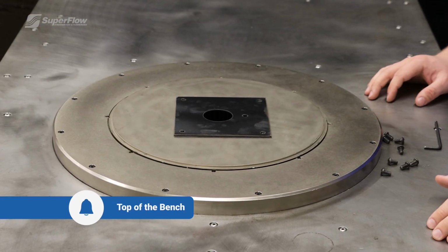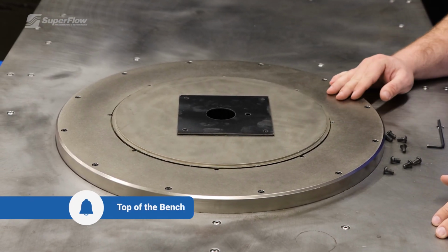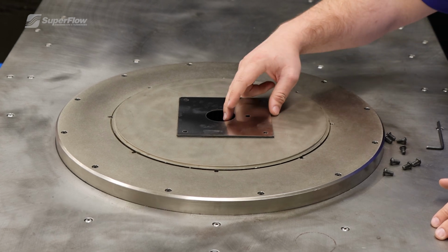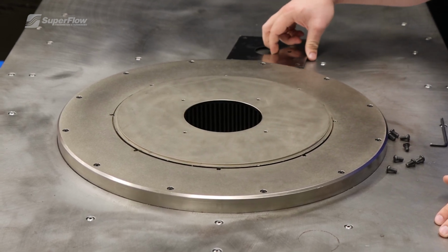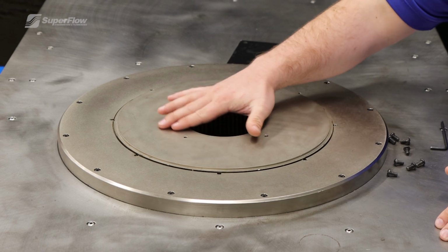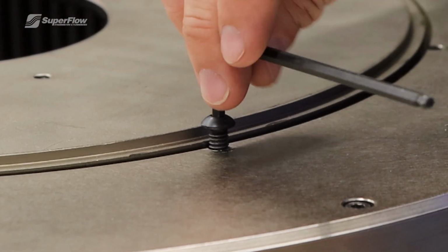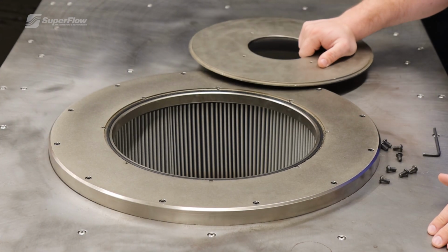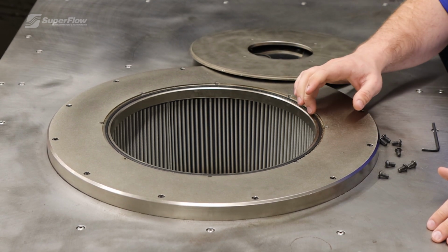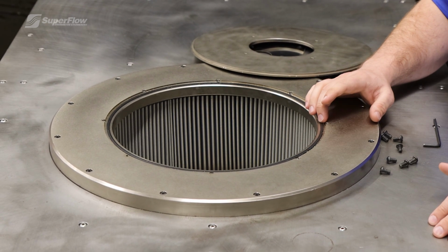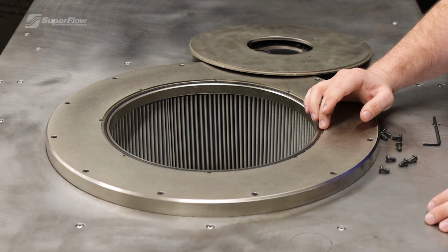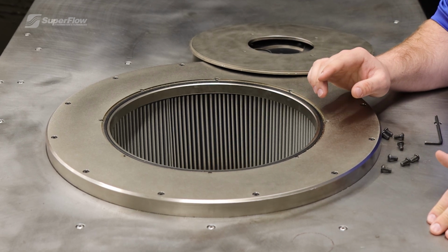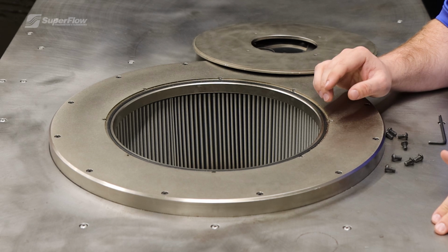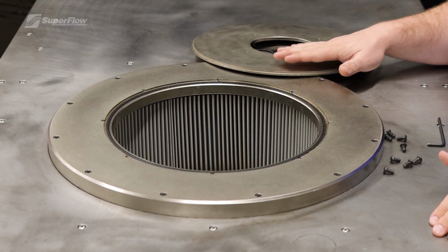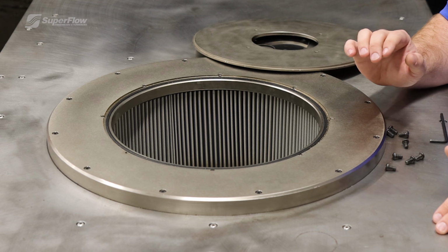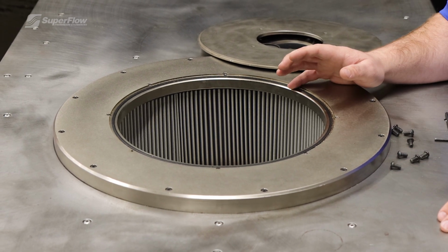Moving to the top of the bench, you see this is our Orifice plate assembly. On top right here, we have our daily reference plate. Beneath that is the main Orifice cover. It is housed under 8 screws. I removed those already. And beneath that, you'll find your sealing gasket. It's important to inspect this frequently for any cuts, cracks, or imperfections, because this is the main sealing point underneath your cover plate. And if anything is leaking, it'll cause misreadings in your calibration.